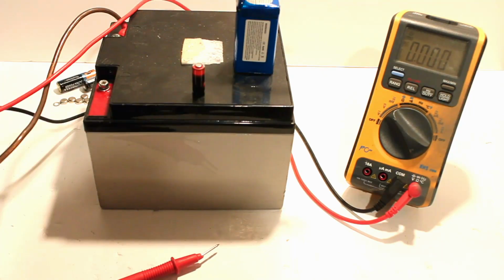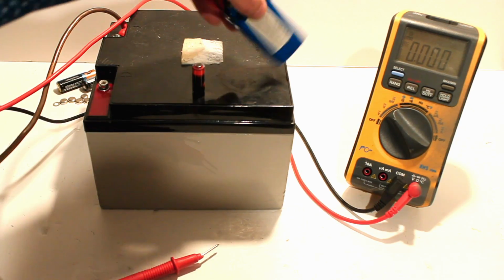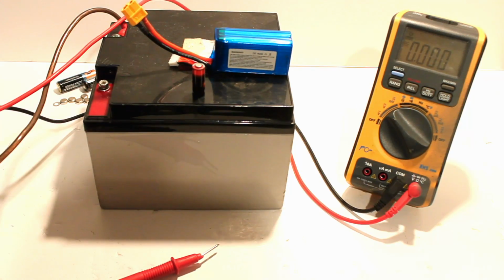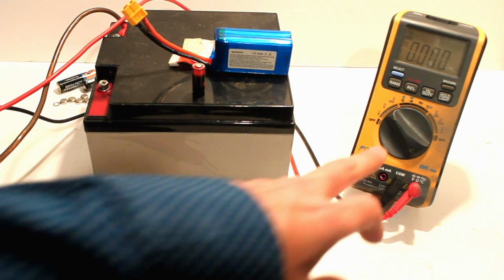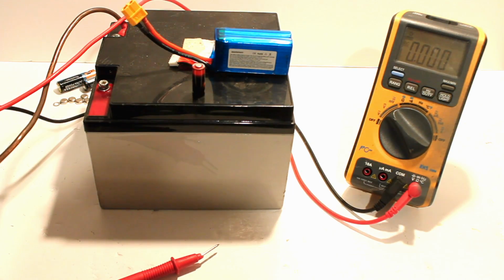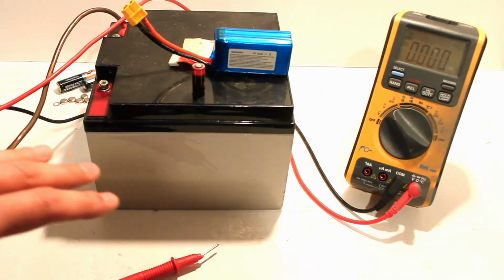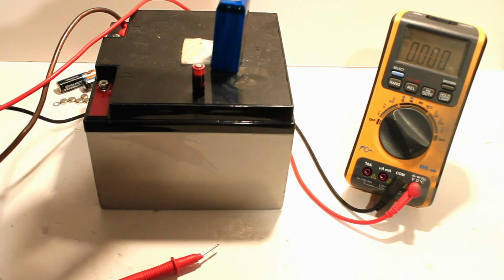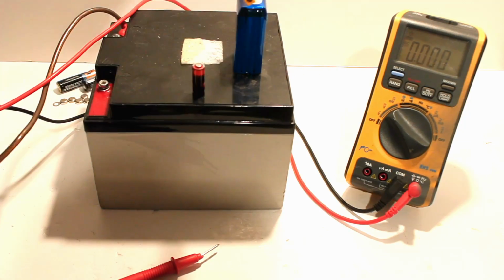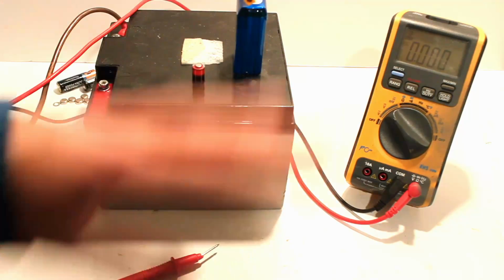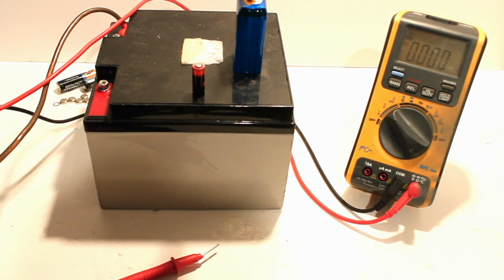We're not going to go into testing the current capabilities of batteries, because one of the things that can happen when testing current capability is you can either blow a fuse or cause a fire, because amps means power, power is high watts, and watts is heat. Essentially, if I create a small circuit to measure the power from one of these batteries, I'm basically just creating a small electric heater, and if it's not managed well, it will catch fire and blow the battery up, blow my multimeter up, or set fire to my house.